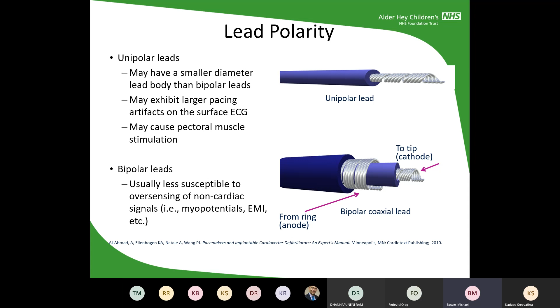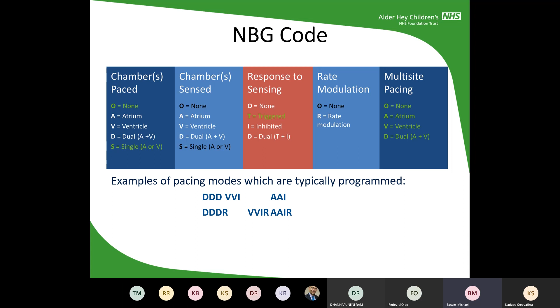So moving on to the coding, we've got the usual codes that people will have heard of: DDD, VVI, AAI, and then the rate response modes. So the same modes, but with rate response switched on. When you see the initials for pacing, the first letter is the chamber that is paced. The second is the chamber that is sensed, and the third is what you do to that sensed beat. The fourth is rate response or no rate response. We generally tend not to use the fifth, multi-site pacing letter, but obviously A is atrium, V is ventricle, and D is both.